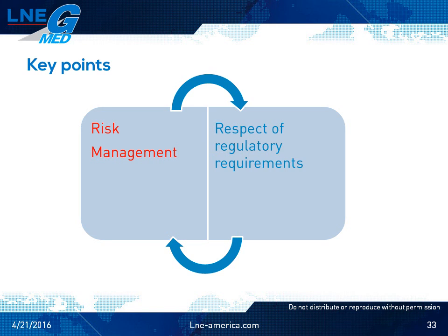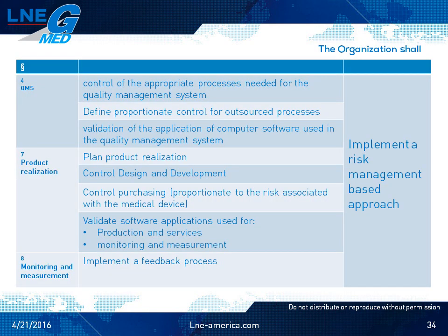So now let's talk about the second major modification, the integration of risk management through the standard. The implementation of a risk-based approach is extended to the provisions of the quality management system itself, in various stages of design, product manufacturing, and to the post-market follow-up. Just a quick reminder here, when the standards refer to risk, it is a risk linked to the safety or performance of the medical device or linked to the compliance with applicable regulatory requirements.